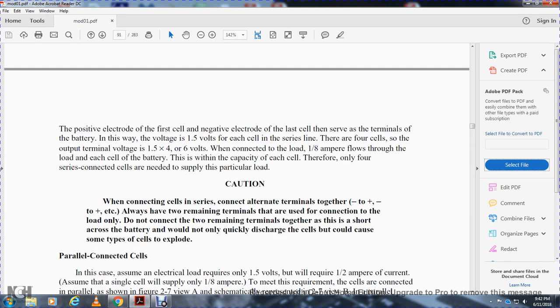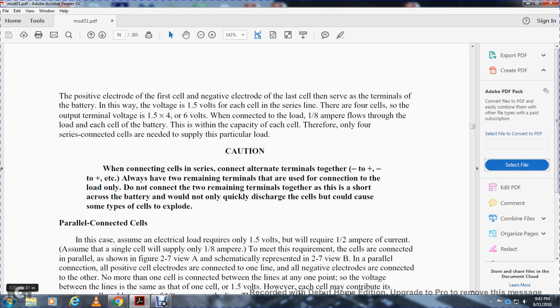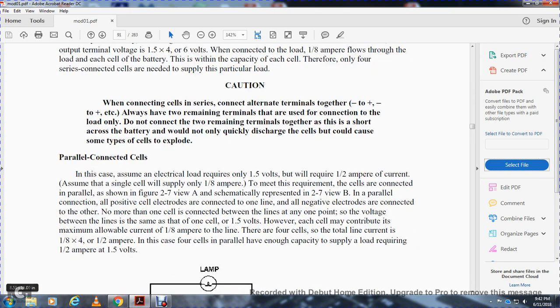Caution when connecting cells in series: connect alternate terminals — positive to negative, negative to positive — always leaving two remaining terminals that are used to connect to the load only. Do not connect the two remaining terminals together as it short-circuits the battery, which would not only quickly discharge the cells but could cause damage or cause the cells to explode.